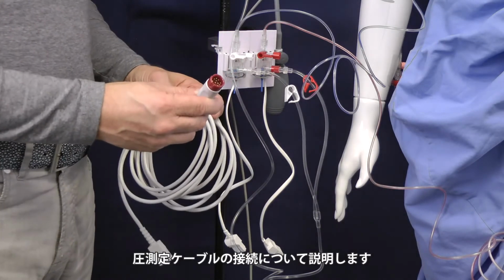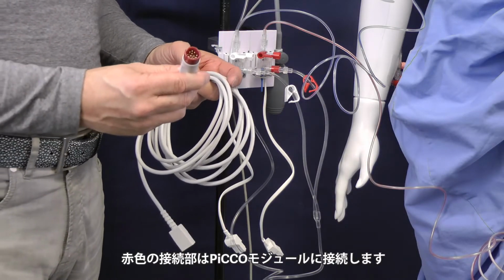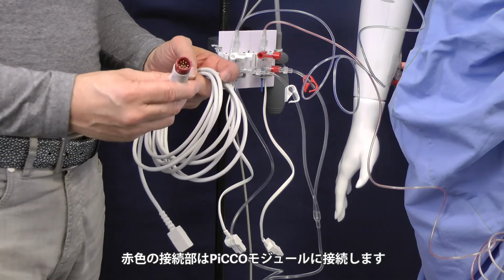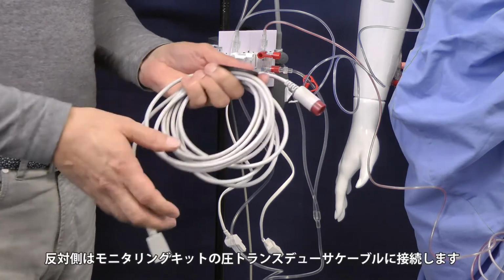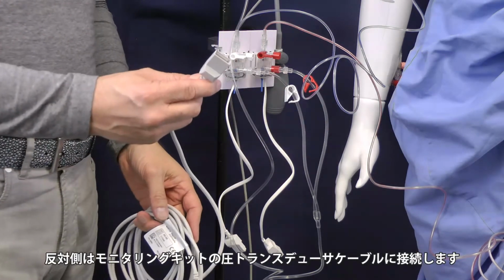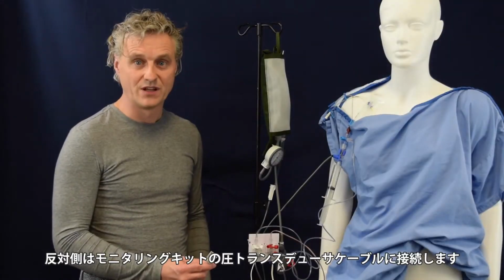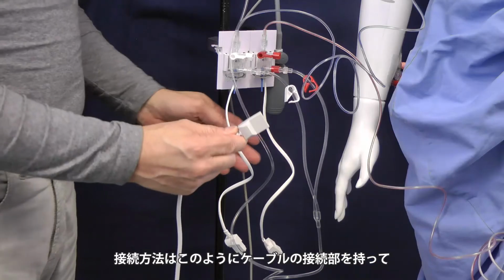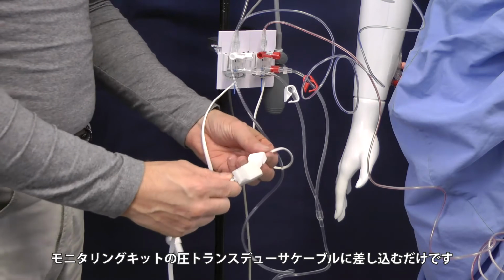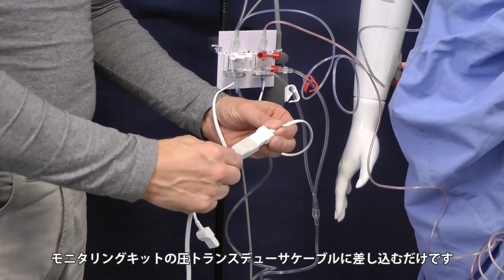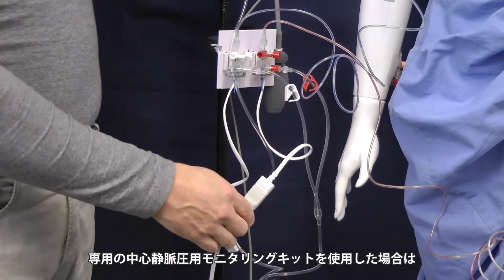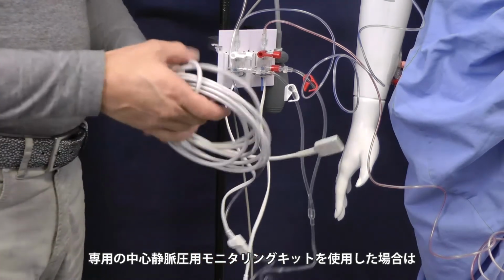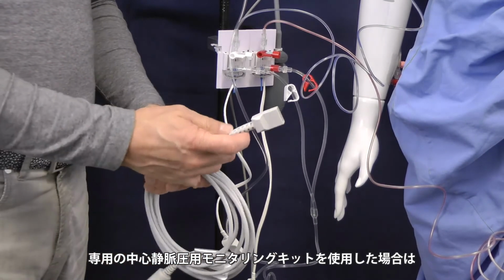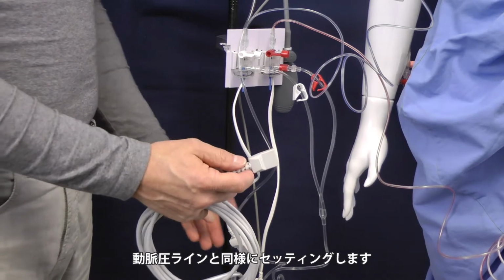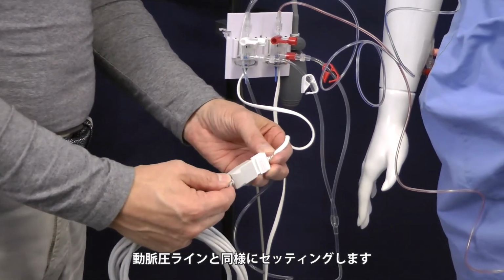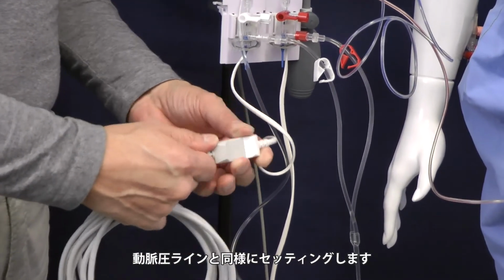This is the correct cable which goes to the entrance of the AP and the CVP on the PiCCO module. The other end we have here where we connect it to the pressure transducer. So just take this connection, take the one from the pressure transducer and connect it like this. Of course you need an extra one, so there's always two cables going to the PiCCO module. Take this one, same as the other one, connect it like this, and it's set.